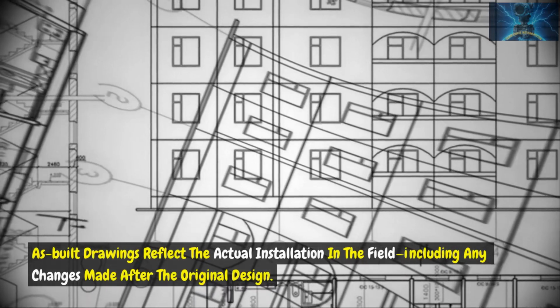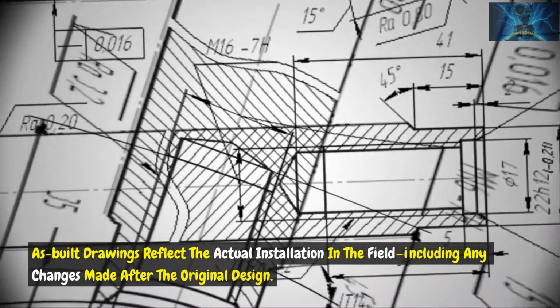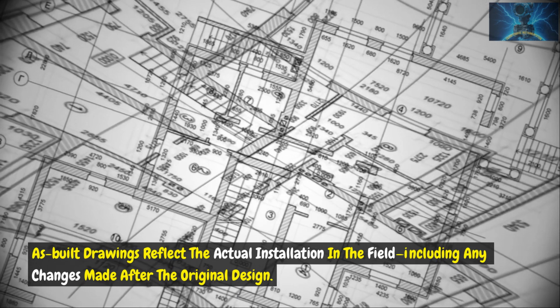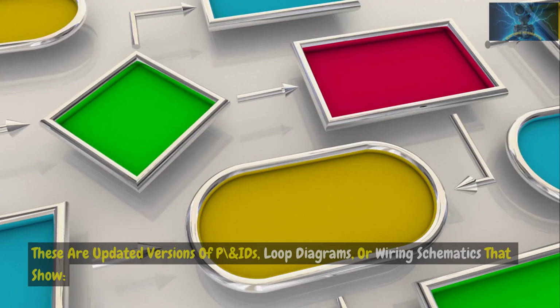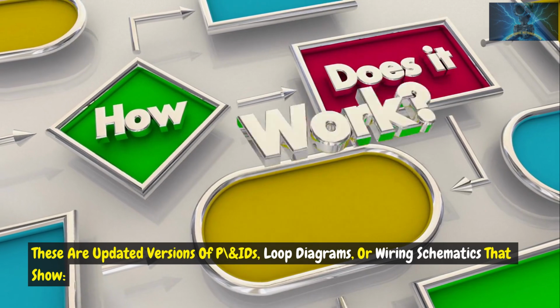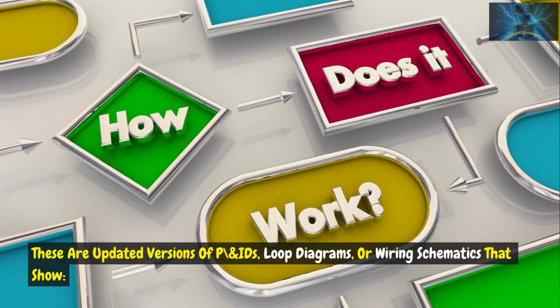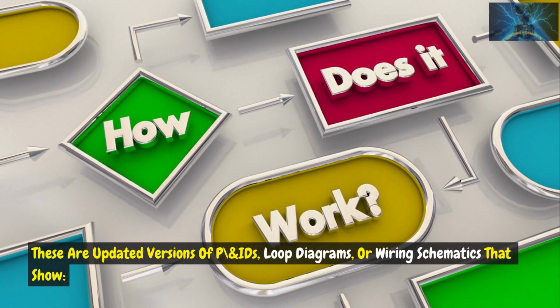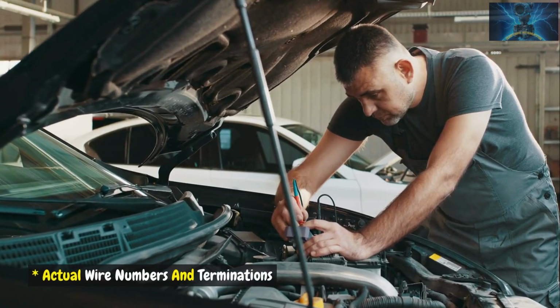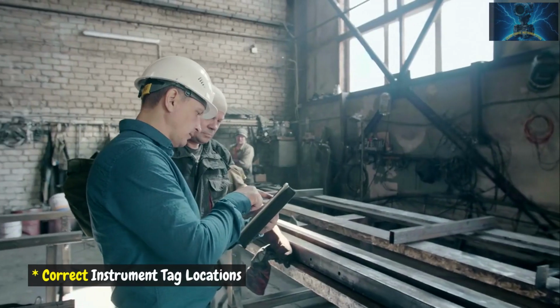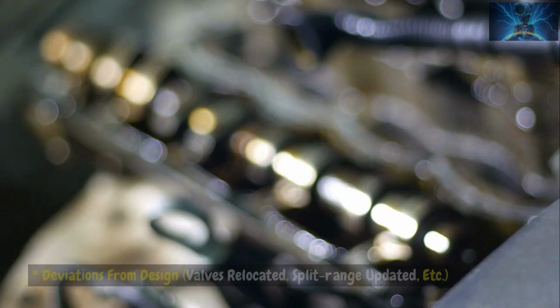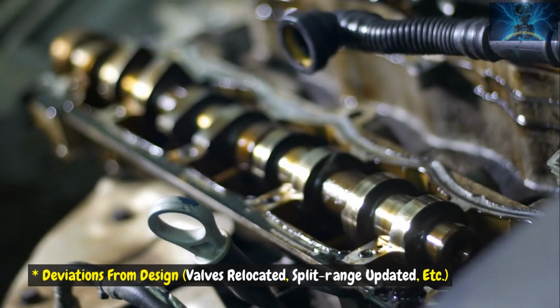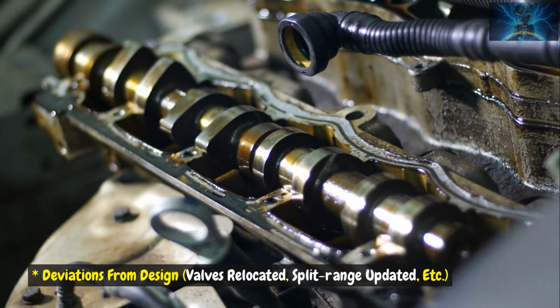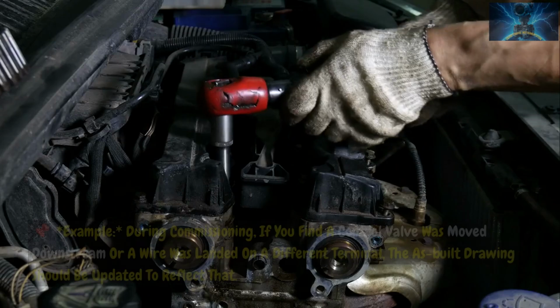As-built drawings reflect the actual installation in the field, including any changes made after the original design. These are updated versions of P&IDs, loop diagrams, or wiring schematics that show actual wire numbers and terminations, correct instrument tag locations, deviations from design, valves relocated, split range updated, etc.